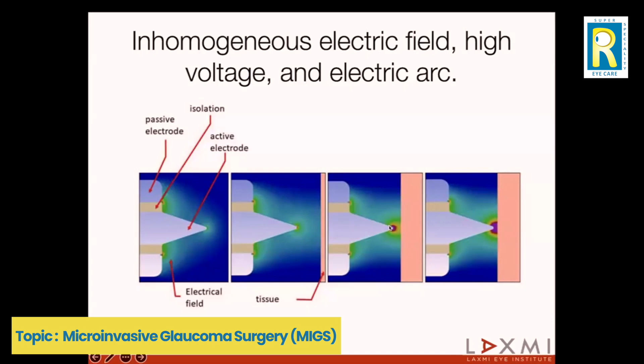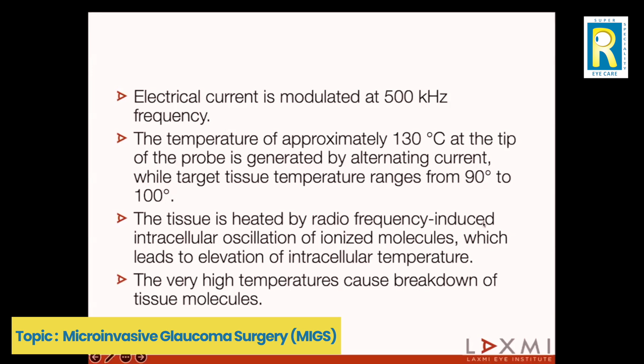Now, the electric current that is generated is at 500 kilohertz frequency. The temperature is approximately 130 degrees at the tip of the probe, and that is generated by an alternating current, while the target tissue temperature ranges from 90 to 100 degrees. So, the temperature at the tip and the temperature at the target tissue are two different things. This tissue is heated by radiofrequency induced intracellular oscillation of ionized molecules, which leads to elevation of intracellular temperature. And it is this very high temperature that causes a breakdown of the tissue molecules.